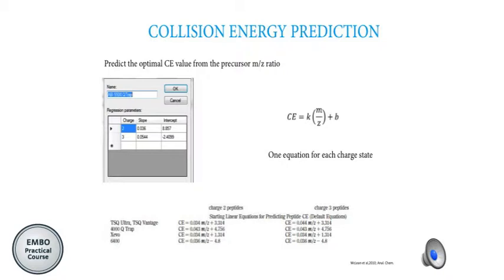We saw yesterday during the tutorial this formula that is in Skyline — this is for the 5500 QTRAP — in which we have a slope and intercept that goes into this formula to calculate the collision energy. We have one equation for charge 2 and one equation for charge 3. This is similar in other instruments and they are usually divided by the charge of the peptide.